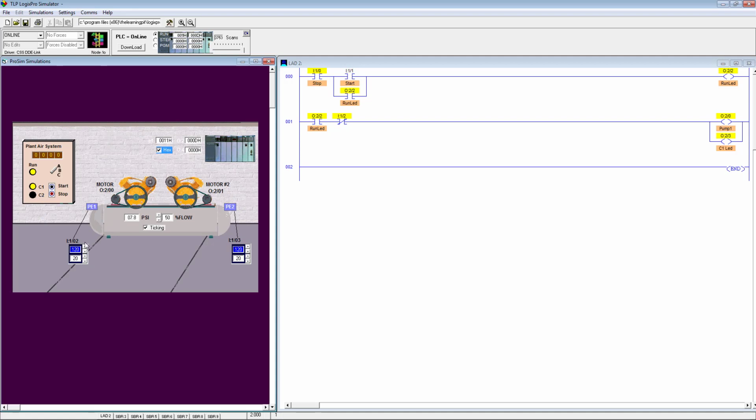It will take it to the upper limit, which is 120 psi. It's continuously increasing, and it's running. C1 is glowing up. So let's see whether it will stop at 120 and start back again when it drops down by 20 psi. So let's wait till it reaches 120 psi. As you can see here, it already crosses 100 and did not turn off, just because the upper limit is set at 120 psi. So it should stop at 120 psi. Let me increase the flow rate; I had decreased it just to get this reading quickly.